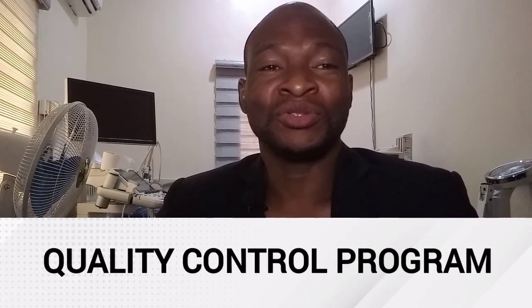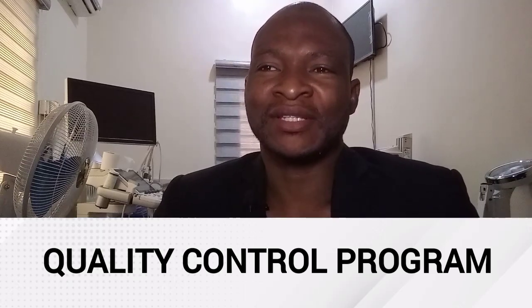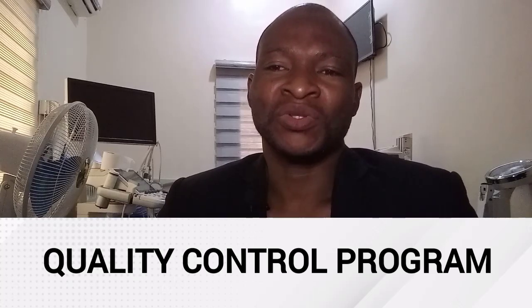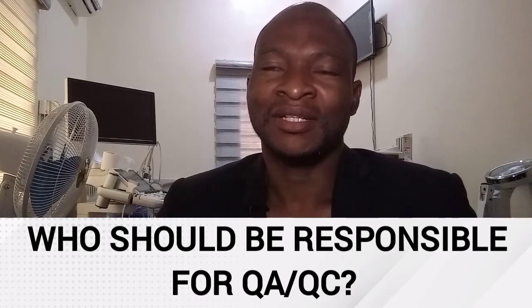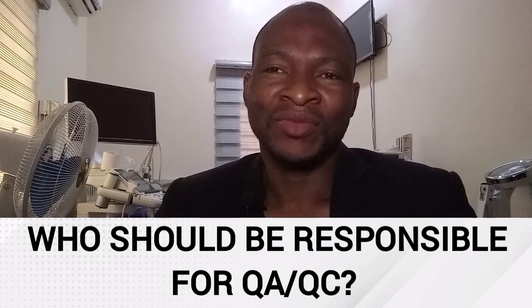What is a quality control program? The function of a quality control program is to help ensure a consistent final image by detecting any changes in equipment performance and having necessary repairs done. So a quality control program is achieved by monitoring and testing equipment at certain time intervals. It also determines equipment operational consistency through time by measuring equipment response to a known test standard.